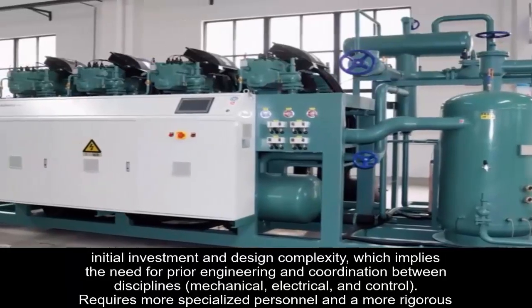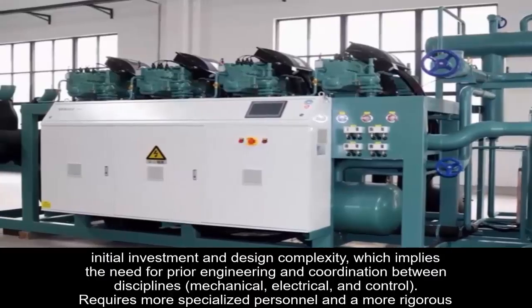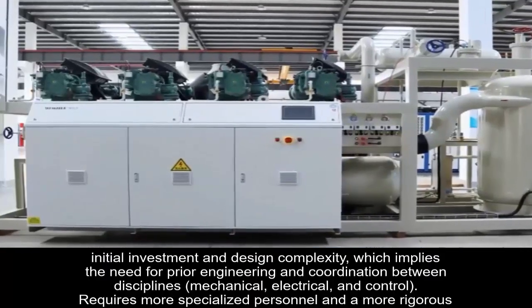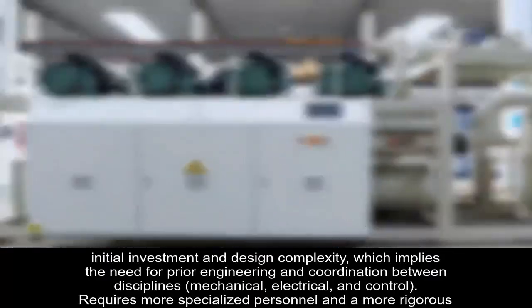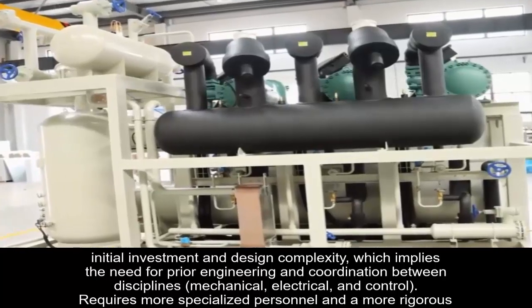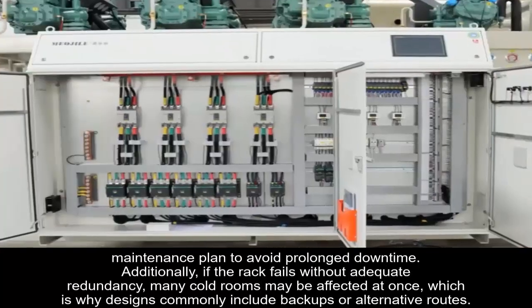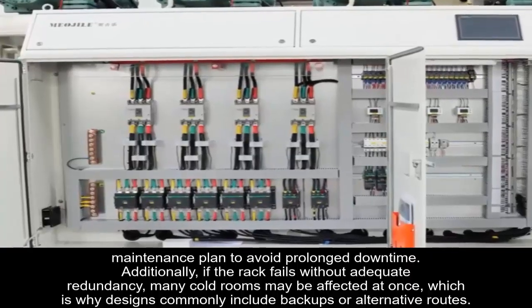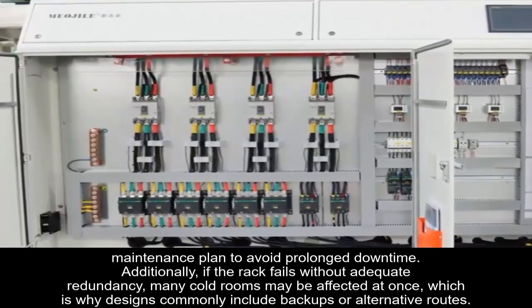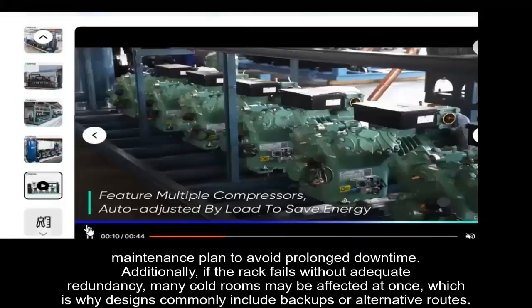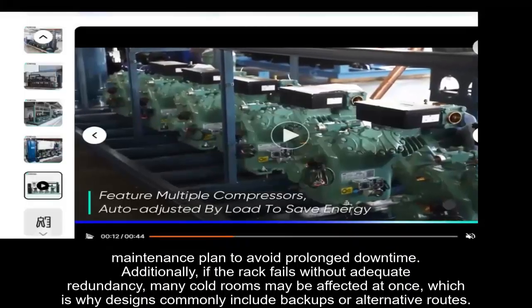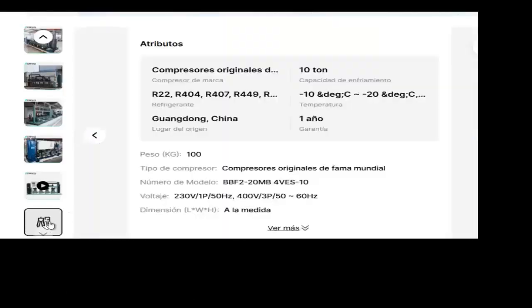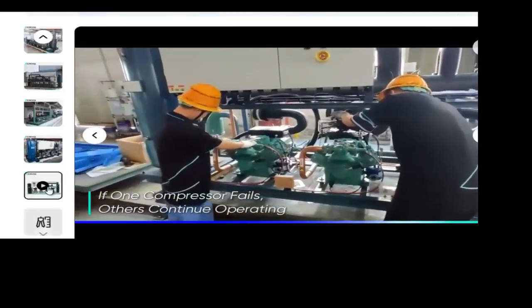Disadvantages: higher initial investment and design complexity, which implies the need for prior engineering and coordination between disciplines, mechanical, electrical, and control, requires more specialized personnel and a more rigorous maintenance plan to avoid prolonged downtime. Additionally, if the rack fails without adequate redundancy, many cold rooms may be affected at once, which is why designs commonly include backups or alternate routes.